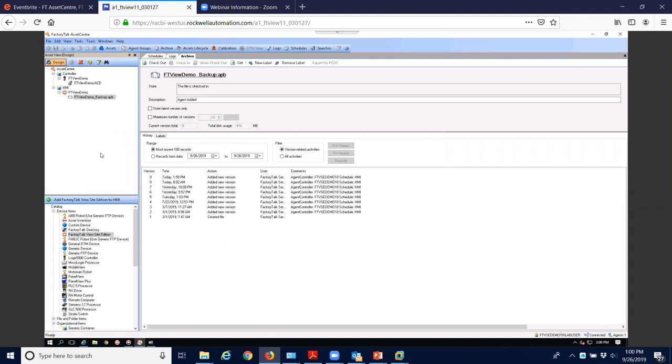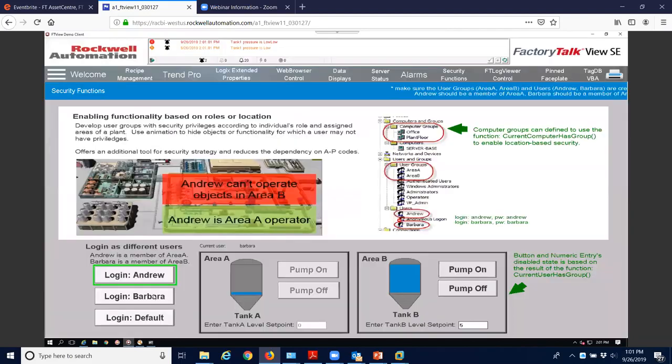So now this will automatically do a backup of the FactoryTalk directory at the same time that it does the HMI. That's a really important step that most people, unfortunately, I made the mistake multiple times. Yeah, so there we are. That's basically what the new stuff in AssetCentre looks like.